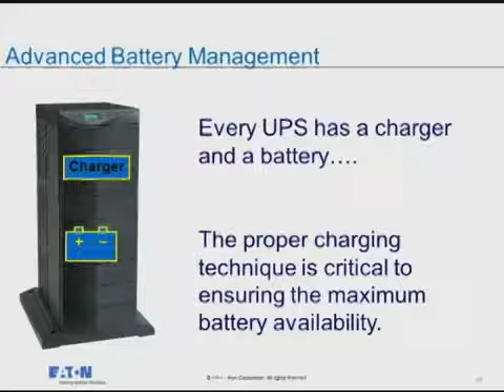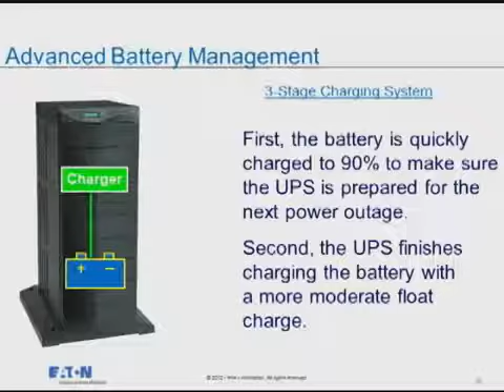What it says is, when I'm completely depleted, I need to get the maximum amount of power back because I don't know when I'm going to need it again. So after a 15-minute power outage, once power comes back, I may have another 15-minute outage, so I need to get as much juice back as possible. So I'm going to do a high rate of charge to get to 90%, then float the batteries to top it up to 100%. Once I have a full battery, I'm going to turn off and let the battery sit there fully charged, and I'm going to monitor it. If I need it, the charge is still there with the power. But if I don't need it, I'm going to monitor it, and once I reach another set point, I'll start the process again - charge it back up, top it up, turn off.